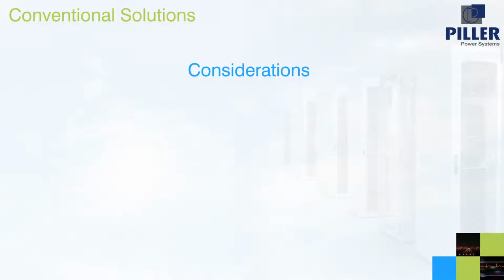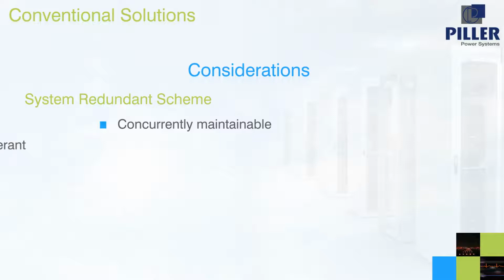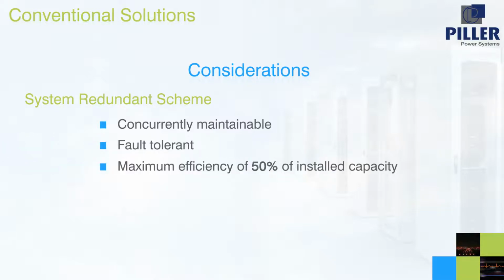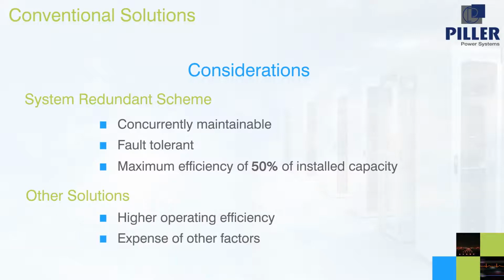For example, a system redundant scheme, whilst being concurrently maintainable and fault-tolerant, has a maximum efficiency corresponding to just 50% of installed capacity. Other solutions like isolated or distributed redundant can have higher operating efficiency, but at the expense of other factors.